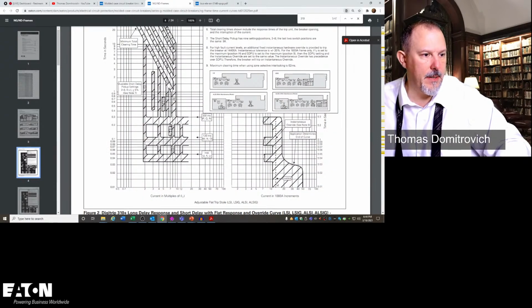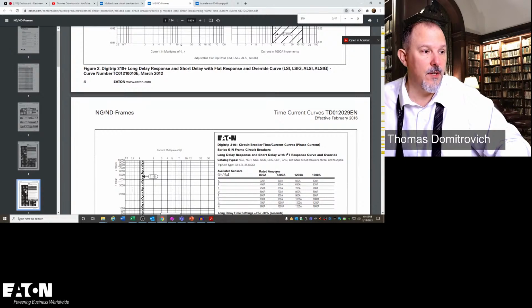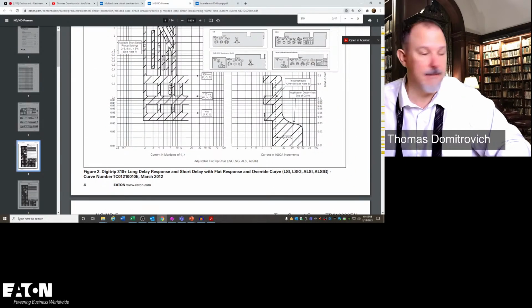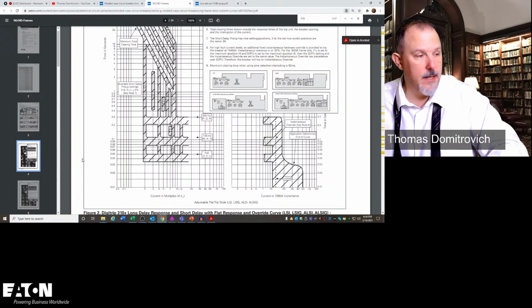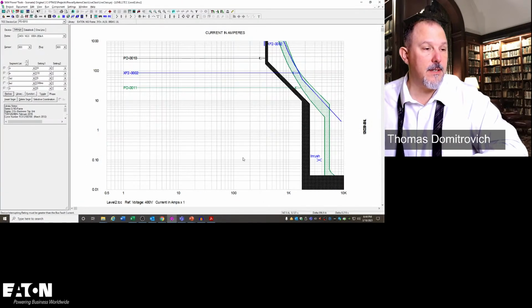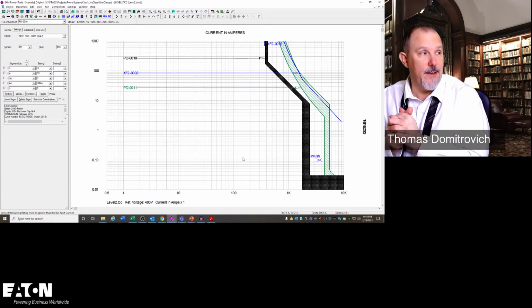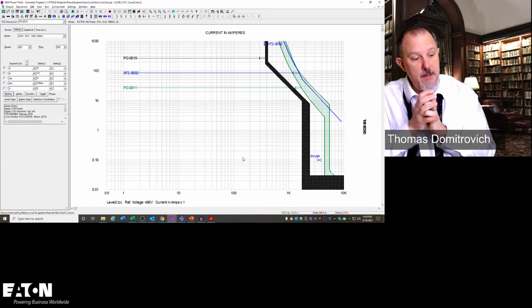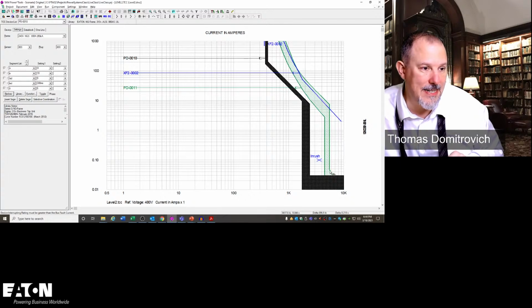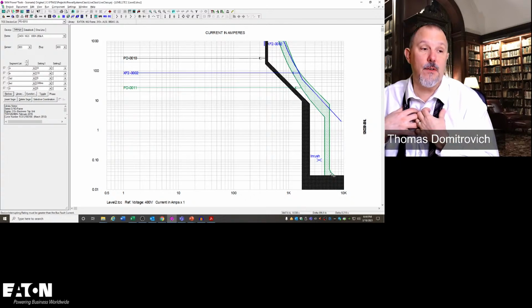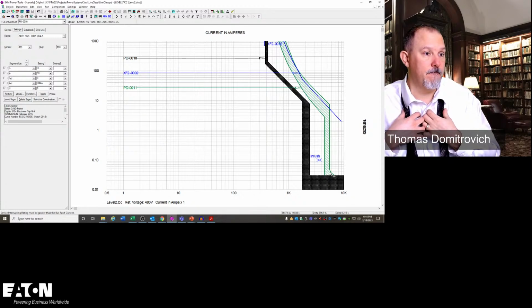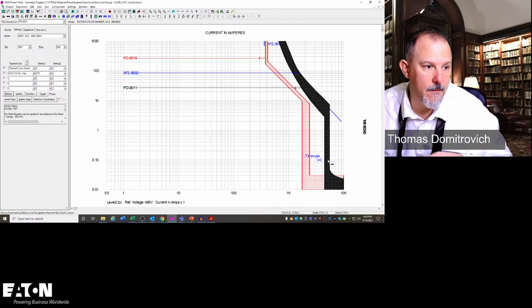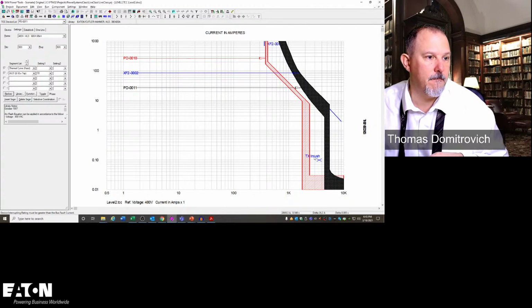And now I come into, and we don't show you what goes on below 0.01 seconds. So I am somewhat in a little bit of a sticky wicket, because I'm at 5,500 amps. I am right here. I know that I would feel comfortable, but I would have a hard time picking that breaker. I don't know if I can move the instantaneous over. So my fault current, my 5,500 amps, is about right in here. Man, that's going to be a tough one.